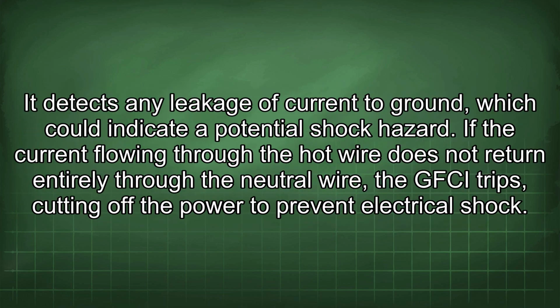It detects any leakage of current to ground, which could indicate a potential shock hazard. If the current flowing through the hot wire does not return entirely through the neutral wire, the GFCI trips, cutting off the power to prevent electrical shock.